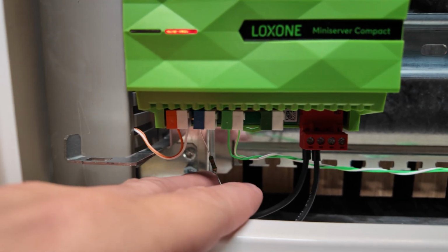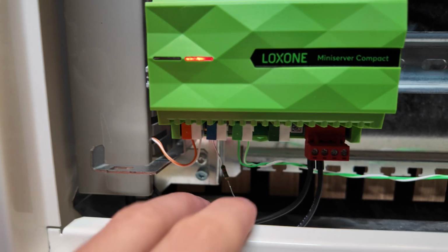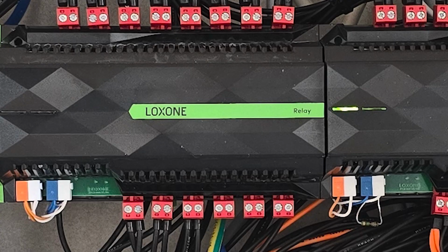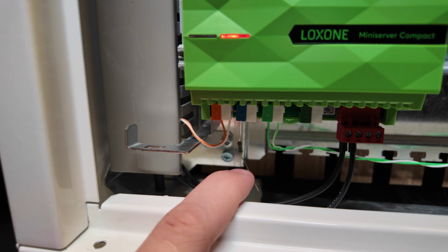At the very end of the Link bus here, the last extension, we need to put a 120 ohm resistor between blue and white. This is against reflections on the bus.